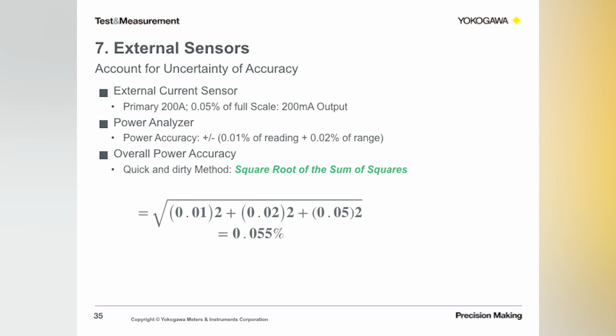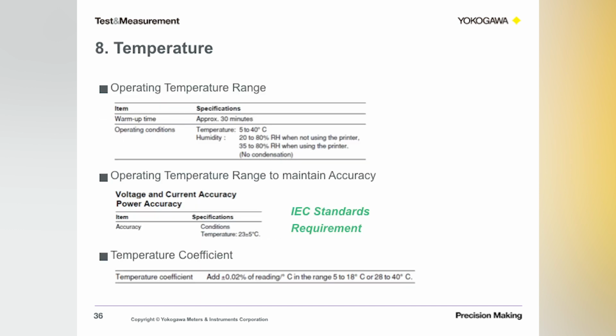So you see how much uncertainty an external sensor can add, because if you were to just calculate 0.01 squared plus 0.02 squared and take the root of that, you would get approximately 0.028 or something like that, right? So adding an external sensor does increase your uncertainty. So, okay, I hopefully explained that subject pretty clearly. What are other factors that could affect your uncertainties?